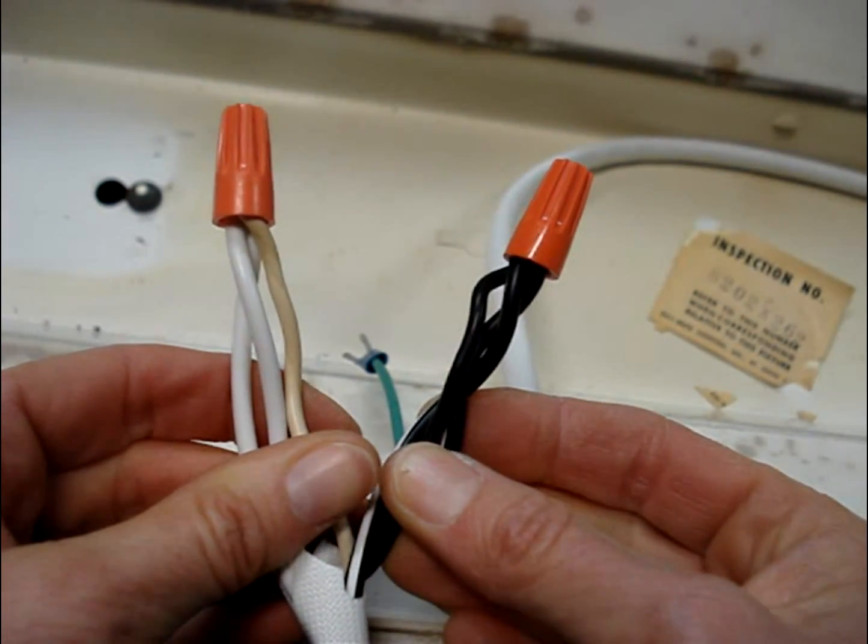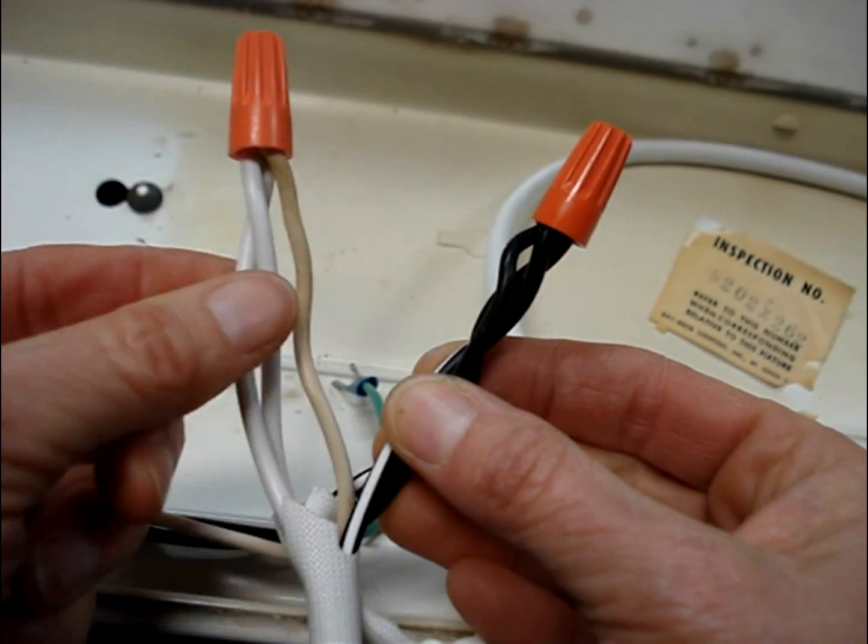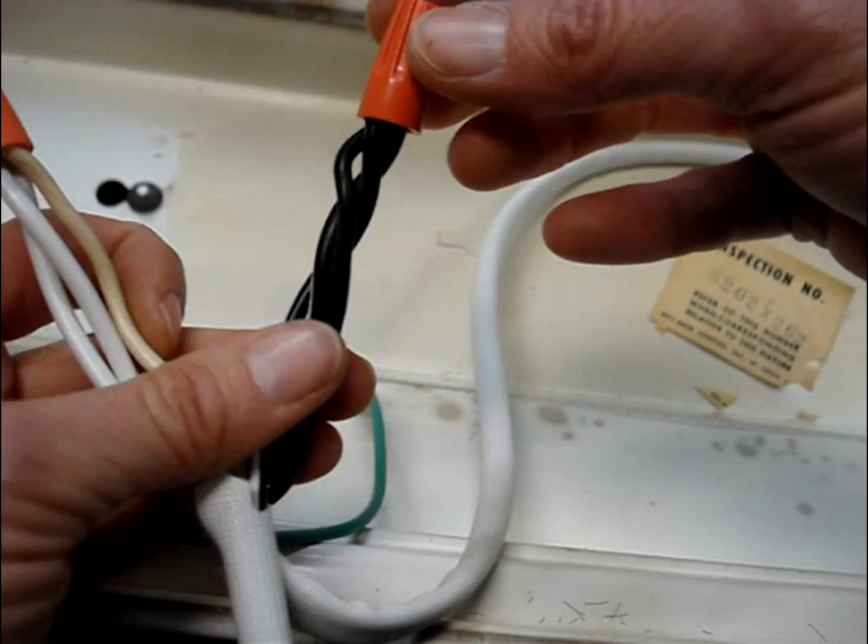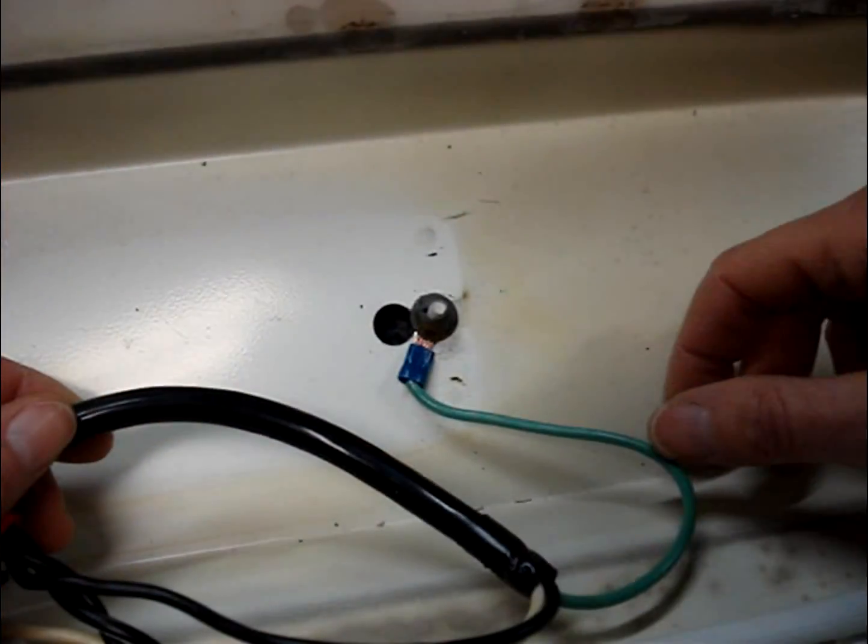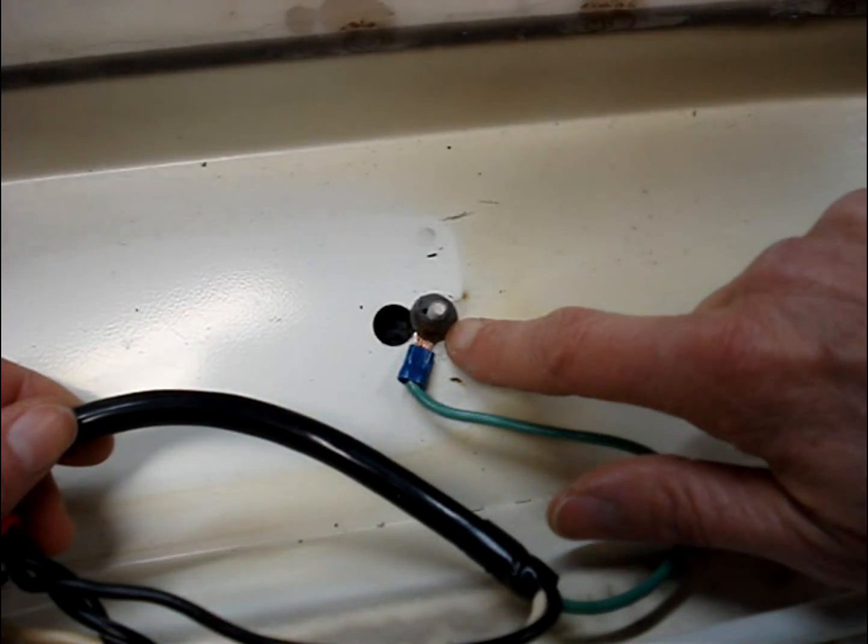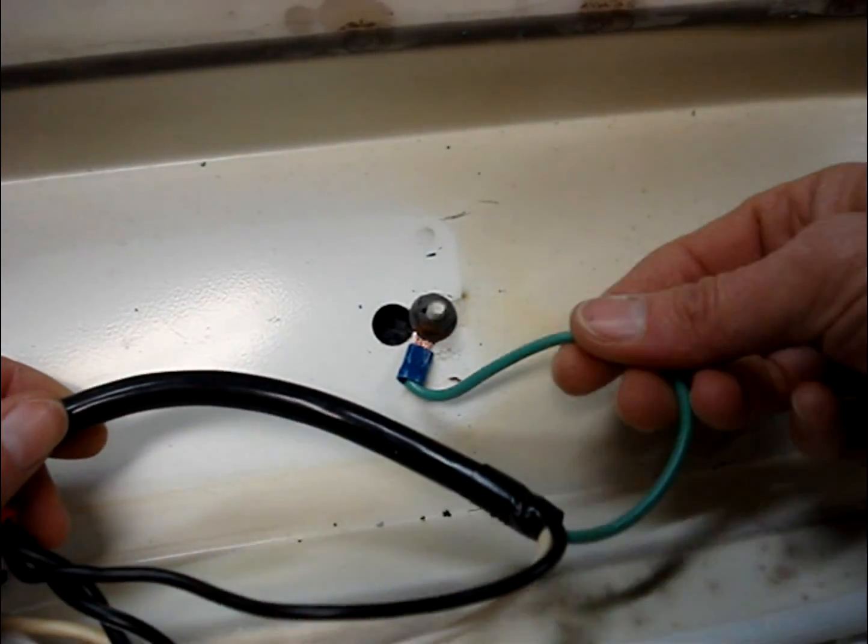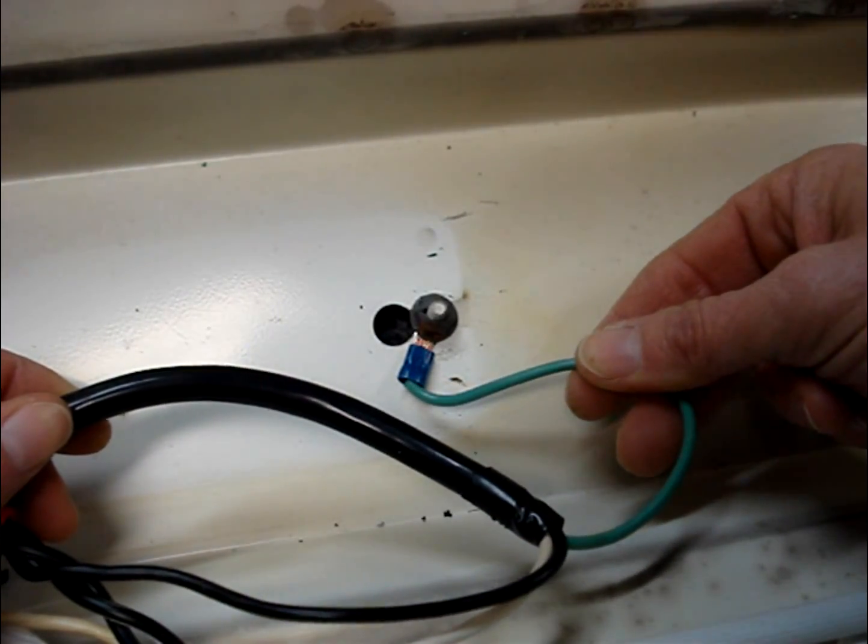Whether you use wire nuts or the push-in connectors, you should have the three white neutral wires connected together and the three black hot wires together. Connect the ground wire to the metal part of the fixture. It could be a green wire or perhaps a bare wire. They're both ground.